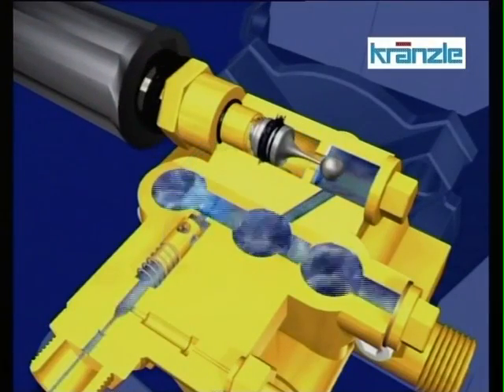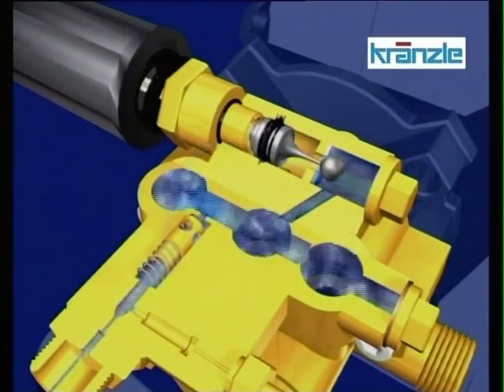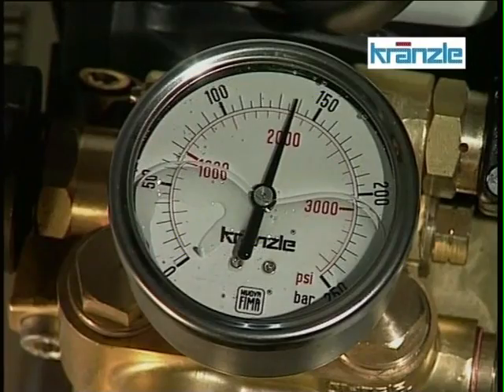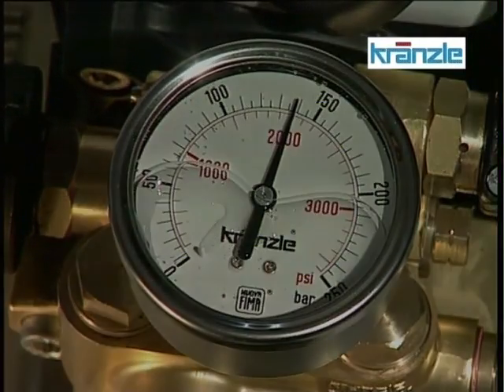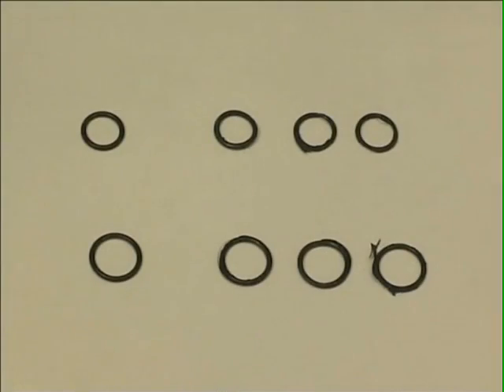The pump does not switch back to the pressureless circuit, the hand wheel can be moved backward and forward, and the pressure gauge shows full pressure. Damages caused by cavitation appear first to the O-rings, so that you can compare. To the left are new O-rings. The other O-rings have been damaged.